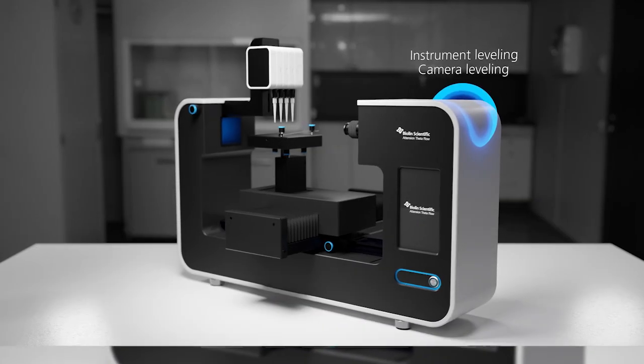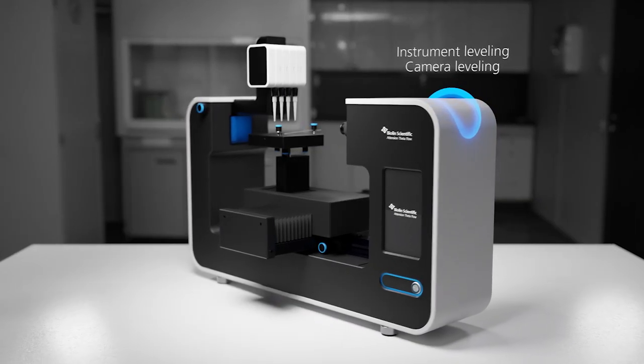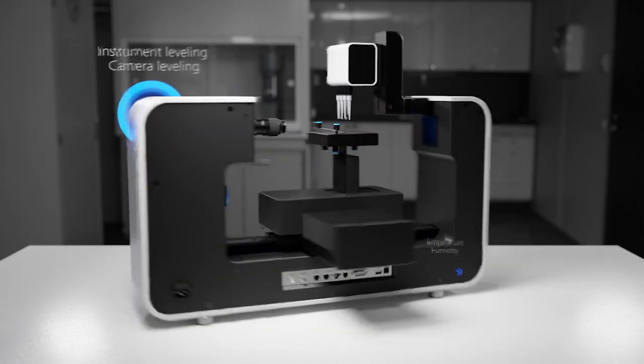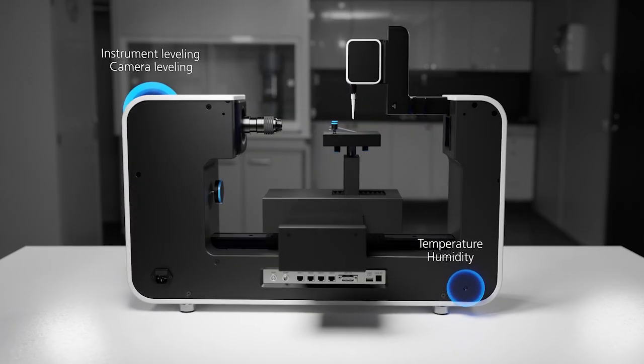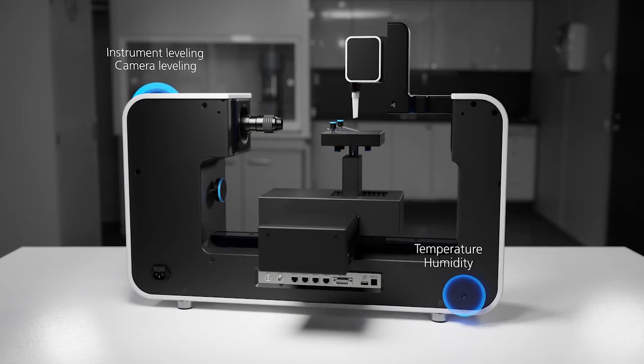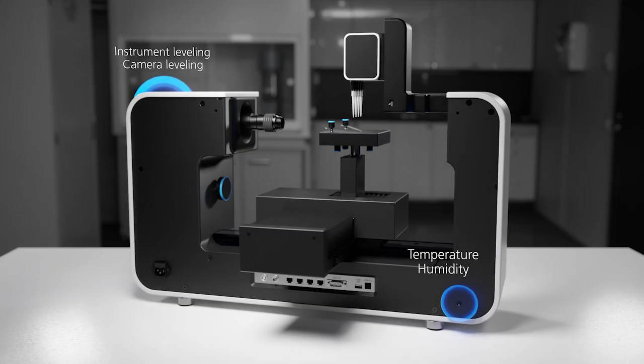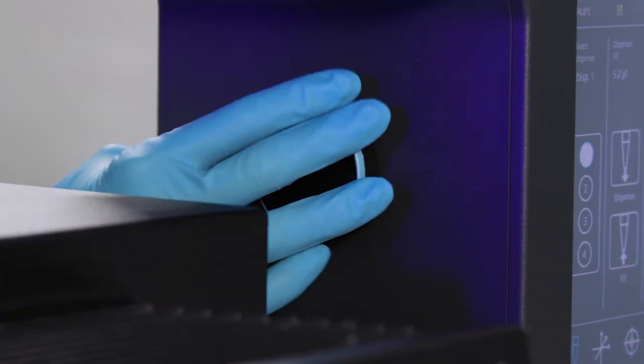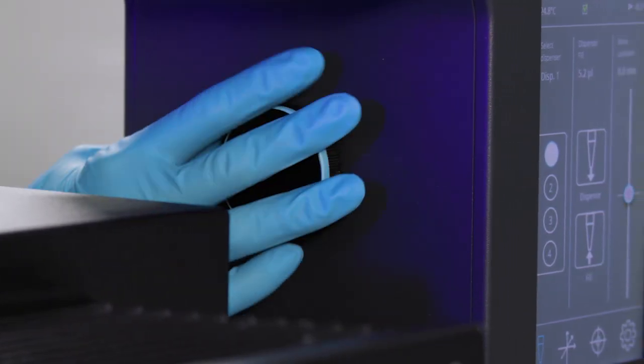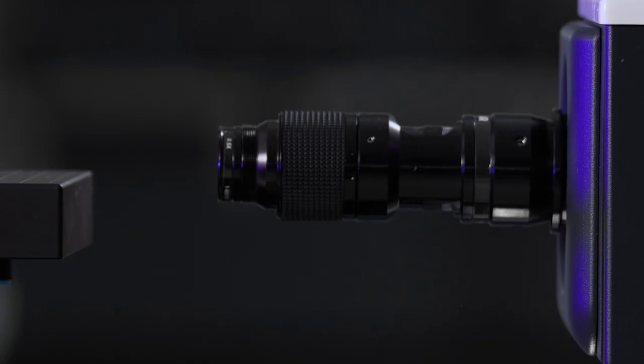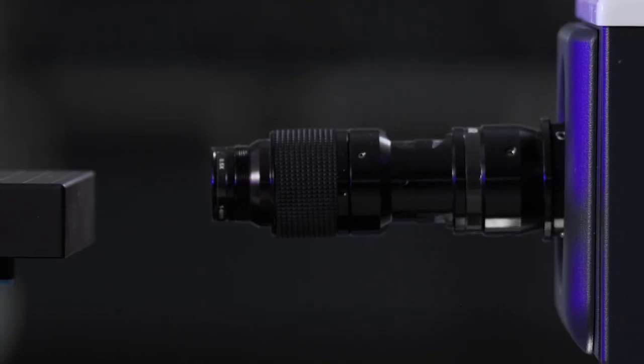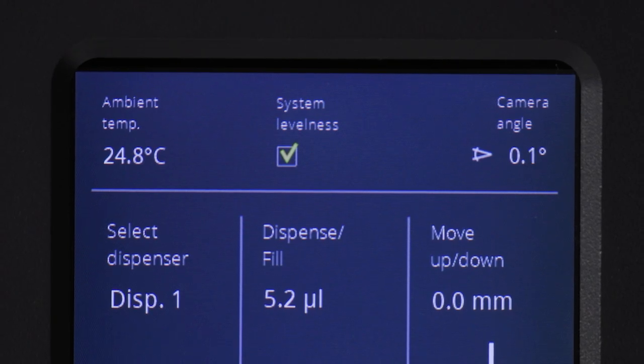Theta Flow has integrated temperature and humidity sensors to monitor the environmental conditions during measurements. This will increase traceability as the values are stored in the measurement files. The leveling of the instrument as well as the camera tilt angle are also recorded. The latter has a direct effect on the results and is thus important to report.